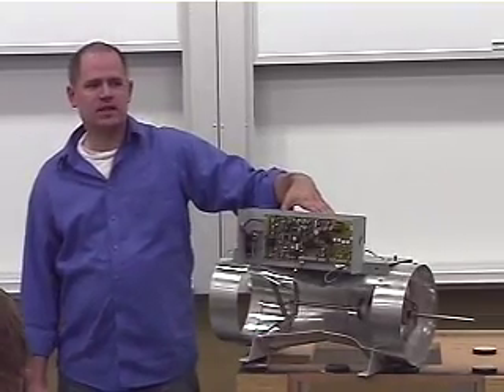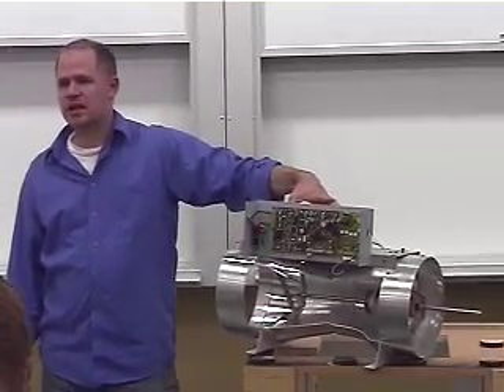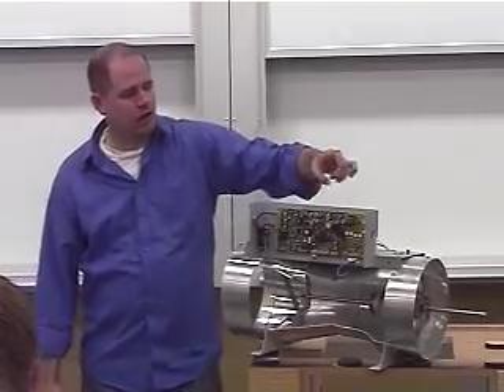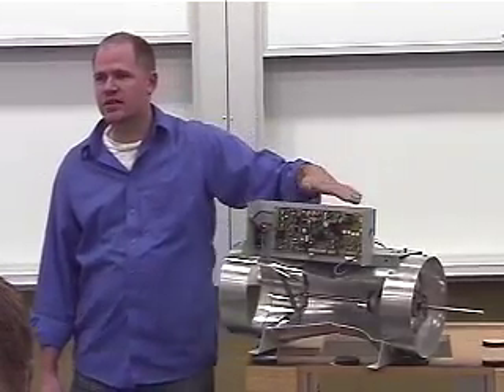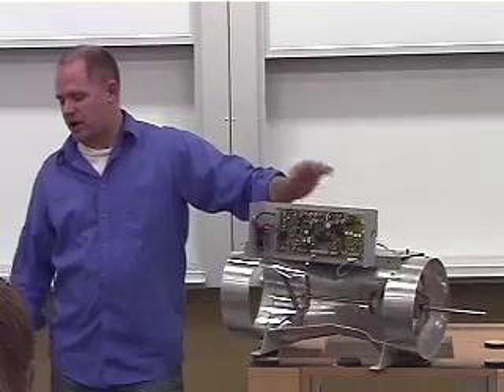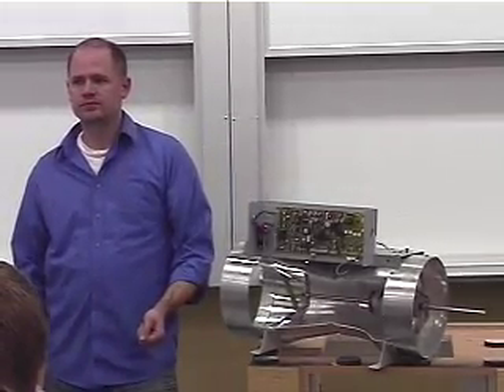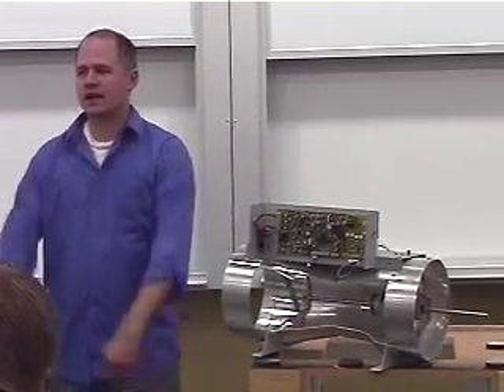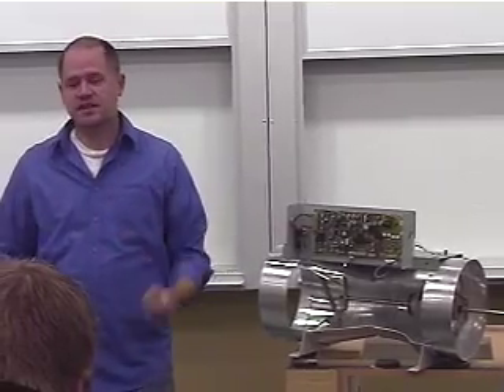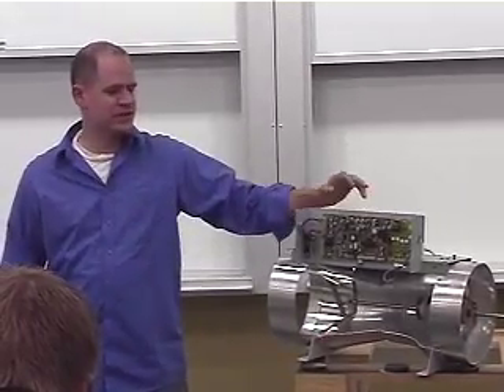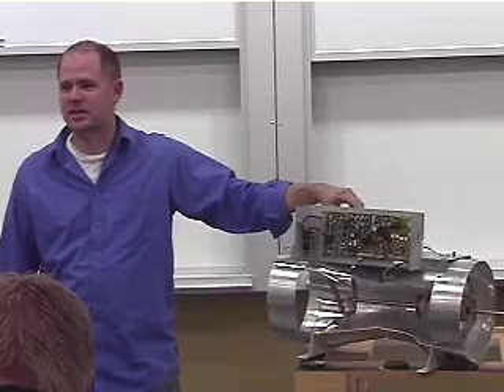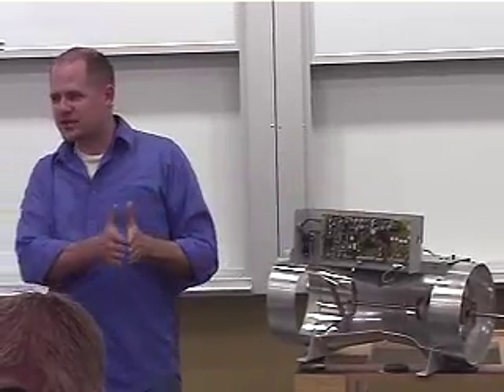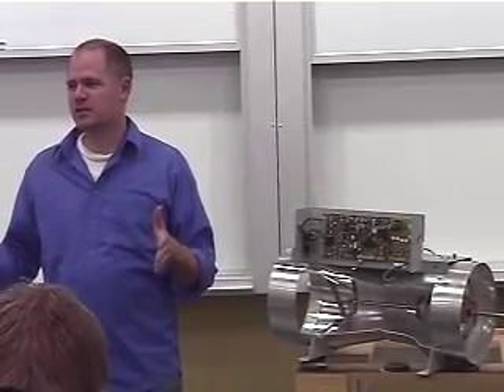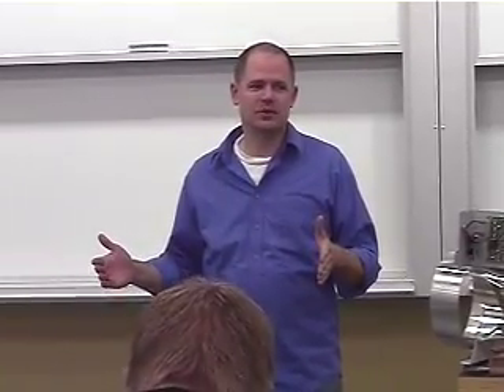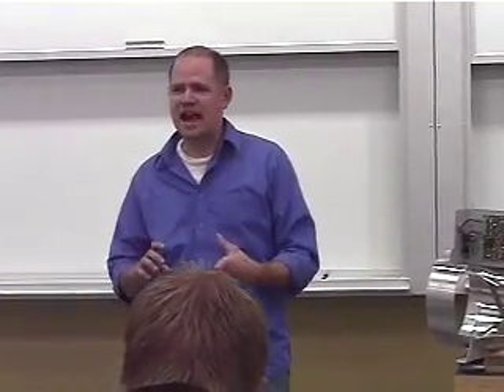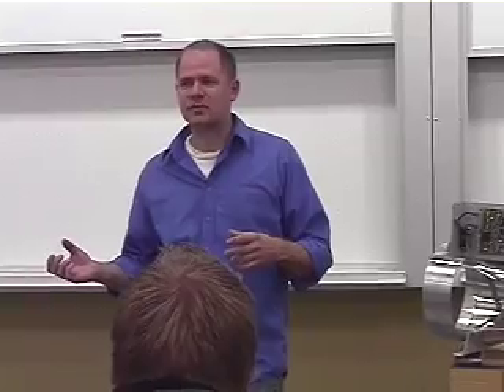The black pistol ones are used on all of the fume hoods because they are a high-speed actuator. They have large capacitors on them in order to get the speed they need to respond to somebody sliding the hood up and down. Because anybody can come in and slide a hood up, and you can slide it up pretty quick, a lot faster than most, or any little damper actuator is gonna move. So you need to be able to respond to that and have the correct flow extremely quickly to maintain the safety of the rooms. That's why they'll have these big black actuators on there that are a linear stroke actuator.